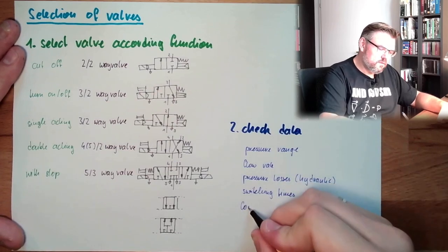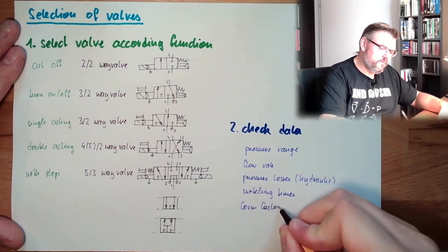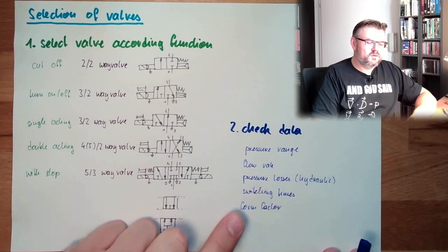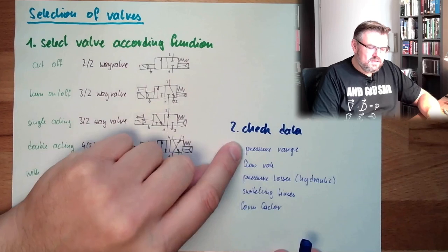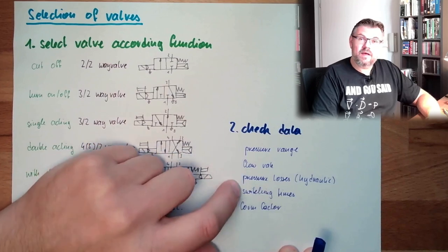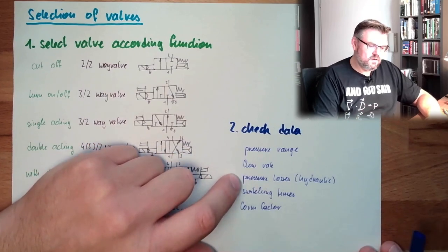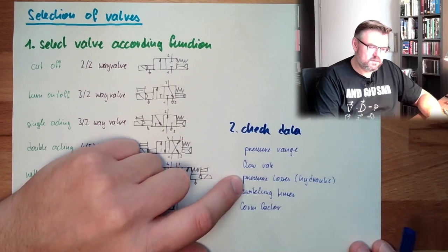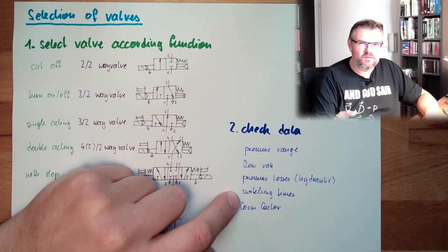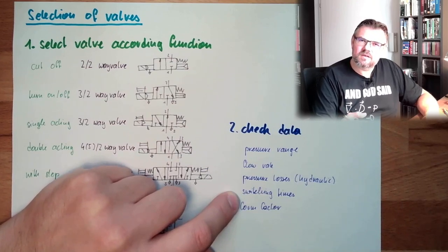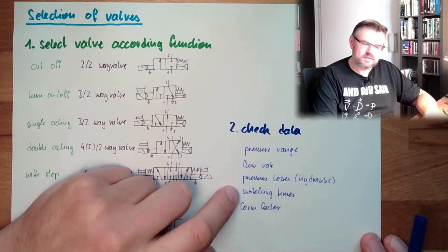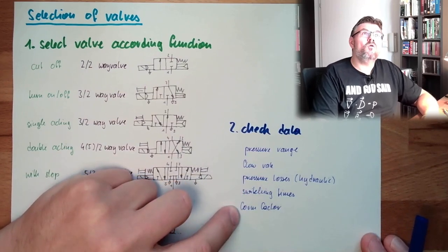Form factor is already something which goes to - this is mandatory: correct pressure range, necessary flow rate, and pressure losses which fit. This is simply mandatory, we cannot work around this. Switching times is usually not that important, you know. If something switches in 30 milliseconds or 35 milliseconds, if it comes to security or safety, maybe in this corner case this is important.